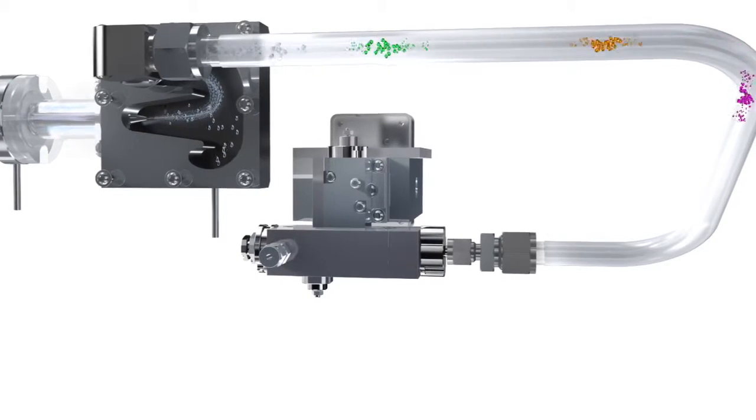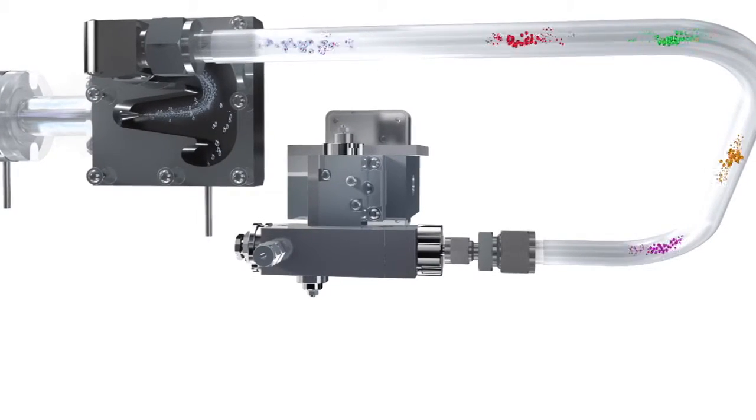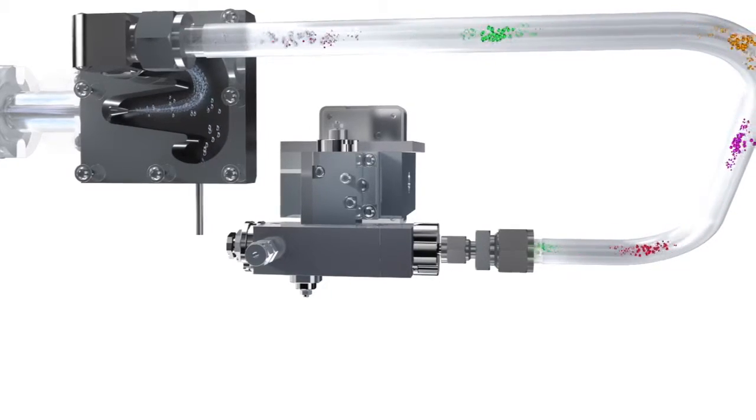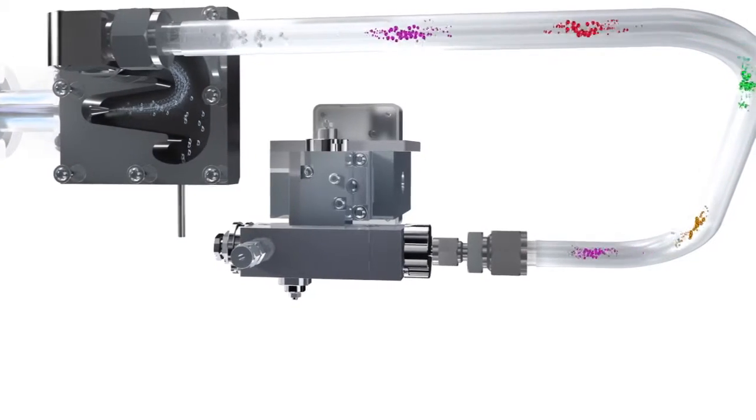The Vanquish charged aerosol detector operates by nebulizing the eluent stream into ultrafine droplets. The solvent is then evaporated to form dried particles.